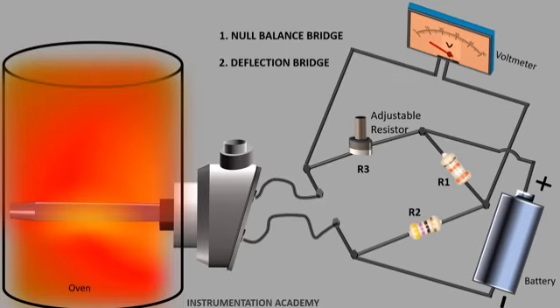As the RTD is inserted into the oven, the RTD temperature increases and correspondingly the voltage indicated by the voltmeter also increases. In deflection bridge, all three resistors are fixed and not adjusted, and the output voltage varies corresponding to the temperature of the RTD. If a voltage transducer replaces the voltmeter, a 4 to 20 milliampere signal, which is proportional to the temperature range, can be generated.